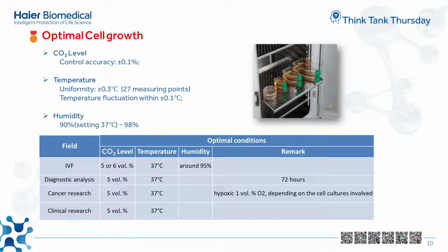Let's take the in vitro fertilization field as an instance. This application aims to fuse an egg and a sperm cell together in a petri dish along with a cell culture medium. The human embryos start to fertilize and develop in the CO2 incubator before being transplanted into a uterus after 2 or 3 days. The optimal conditions in the incubator chamber are approximately 37 degrees Celsius and 5 to 6% carbon dioxide by volume, and the humidity level is around 95%. Staff label the petri dishes very precisely to avoid mix-ups. The inner glass doors of the CO2 incubator mean dishes can be monitored at all times too.